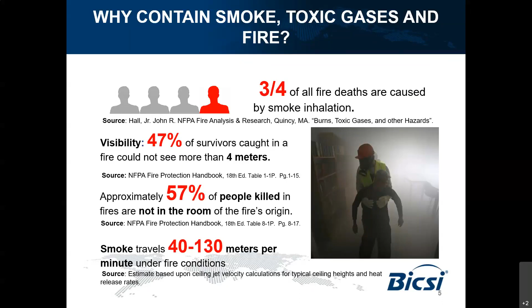Finally, the reason for those figures and statistics is that smoke travels really fast. It can travel up to 40 to 130 meters per minute under fire conditions. Those data come from NFPA, the National Fire Protection Association. They did comprehensive research to emphasize why it is important to have proper fire stopping, to prevent fire and smoke spread through compartments.